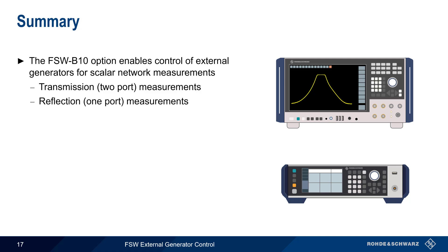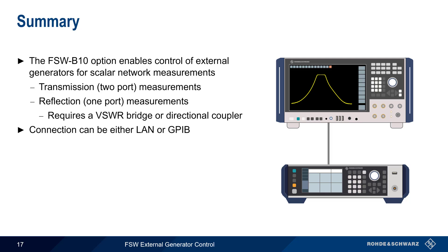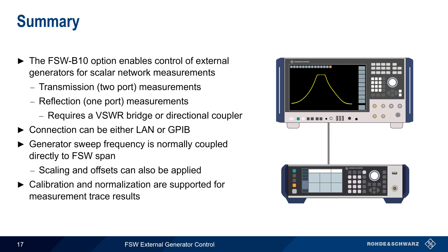Let's end with a brief summary. The FSW-B10 option enables the FSW to control external RF signal generators for scalar network measurements. Both transmission (2-port) and reflection (1-port) measurements can be made, though reflection measurements require an external VSWR bridge or directional coupler. The FSW controls the generator over either a LAN or GPIB connection. The generator sweep frequency range is normally coupled directly to the FSW span, but can be modified by a scale factor and/or an offset. The FSW supports both calibration and normalization of measurement trace results.